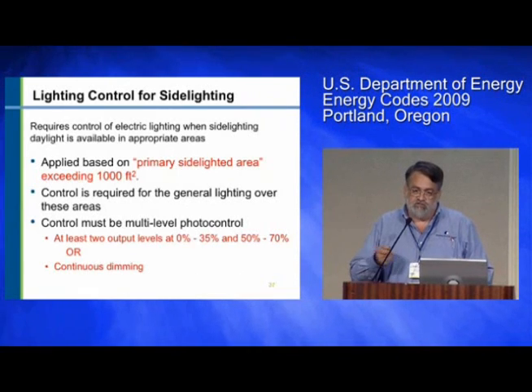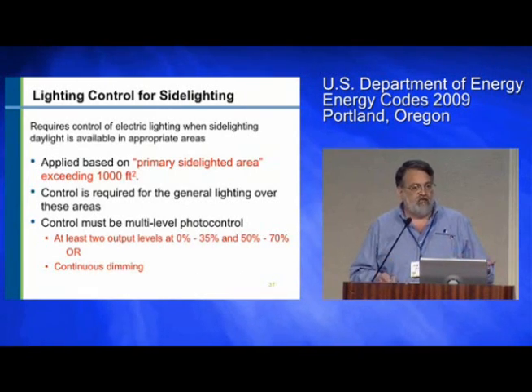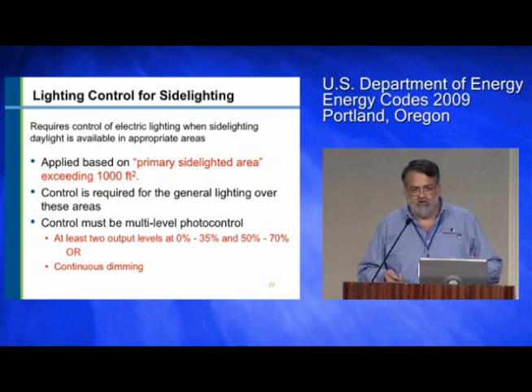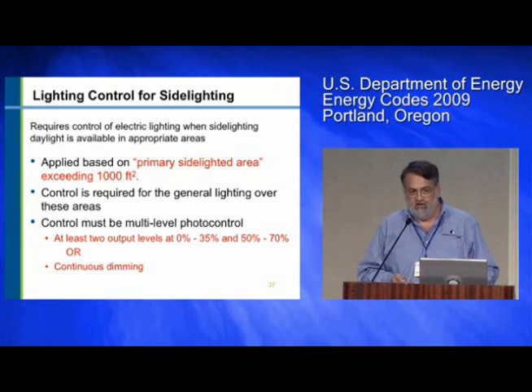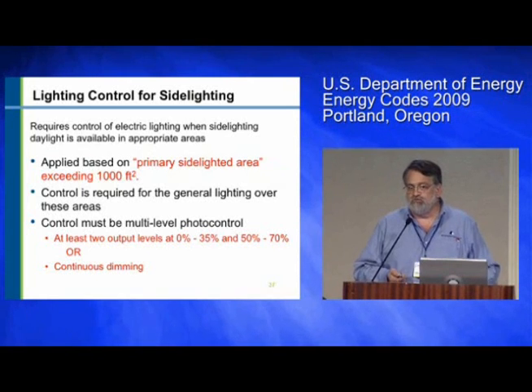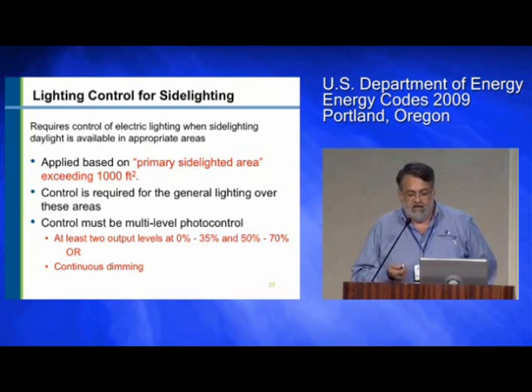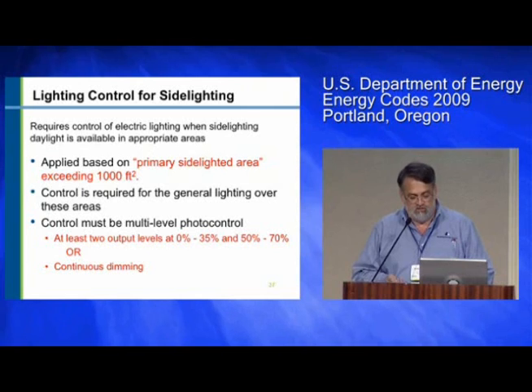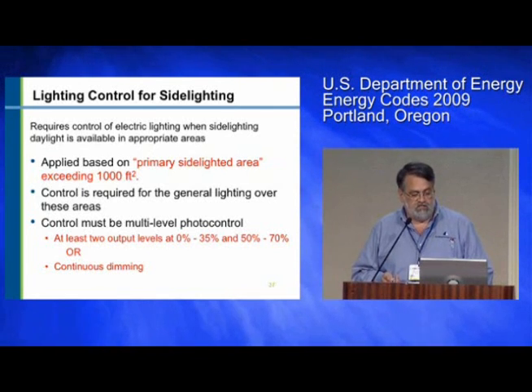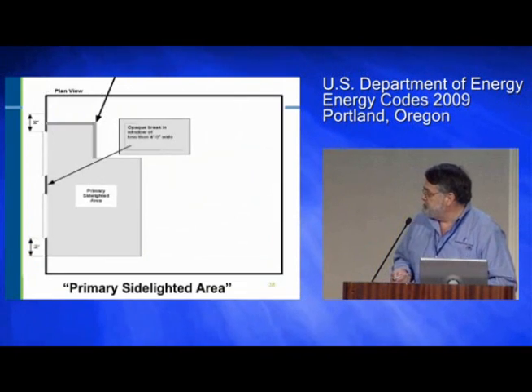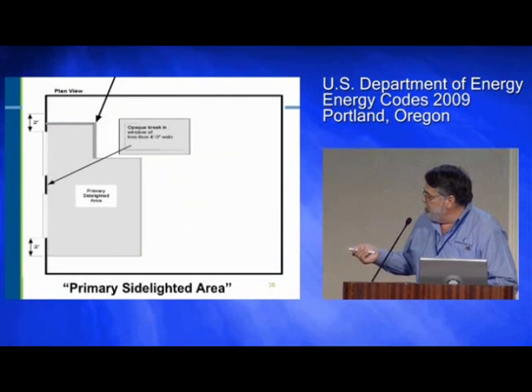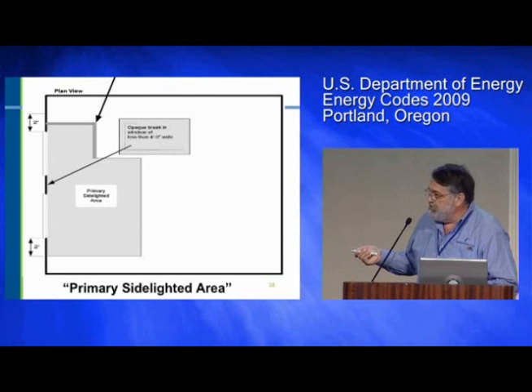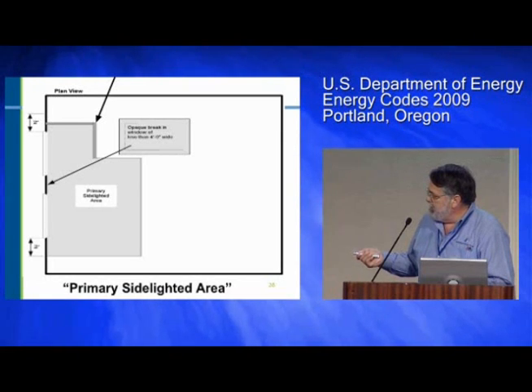So what about side lighting? That was top lighting. For side lighting, if you have windows that meet certain criteria and you have a primary side lighted area, again a definition, then you have to control the overhead lights in that space. And again, it's a similar type of bi-level control or continuous dimming. So what does that look like? Here you have a couple of windows, you have some partitions. If these partitions are 5 foot or higher, that stops the light effectively for purposes of the standard, so you only have to control the light out to that area.